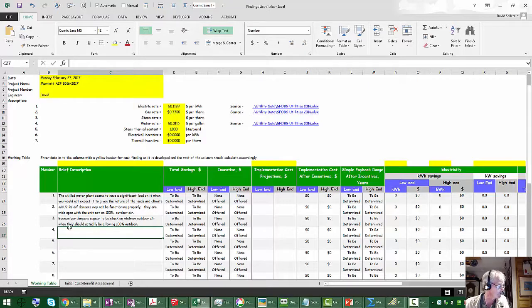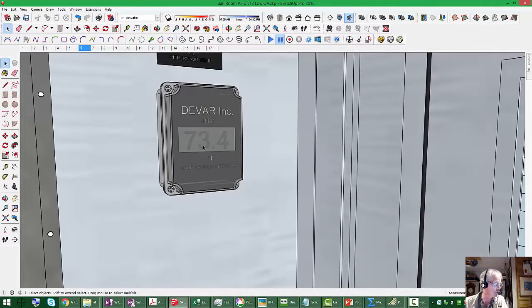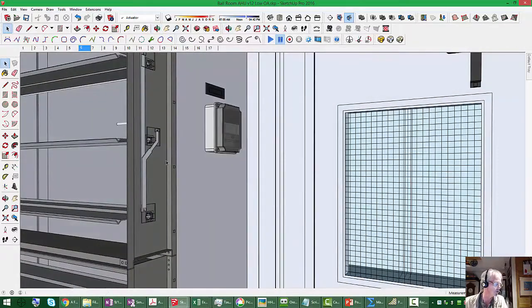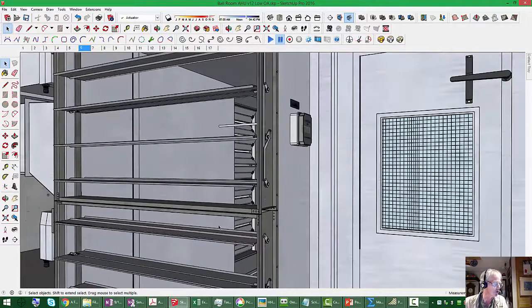Okay, so now our findings list is growing, right? And if you think about that, so if we could achieve the discharge temperature set point by using outdoor air, there's some of that load on the chiller plant that shouldn't be there, right? Because right now we're basically mixing a whole lot of 73.4 degree air. This damper is virtually wide open. Mixing a whole lot of 73.4 degree air with not very much. You can't really assess airflow just by the position of the damper if it's not well sized. But clearly this isn't wide open, so there's probably more return air than outdoor air, so the mixed air temperature probably is closer to the 73 number than not.